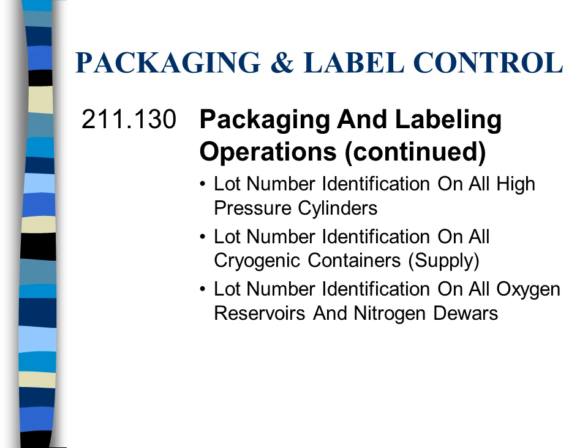Remember I said earlier, the lot number is a code for the total history of the manufacturer of that drug product. Through the lot code, we can learn who filled the cylinders and what day they filled the cylinder. We can go back to the manufacturer and get their records as to when they manufactured that liquid bulk product and what the assay results were for that liquid bulk product.